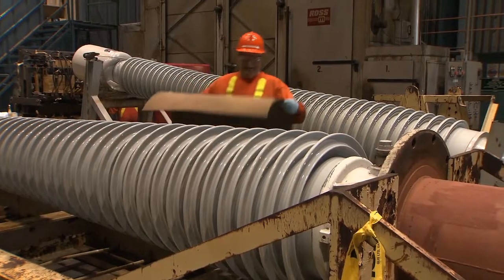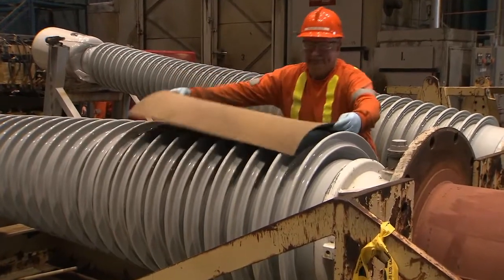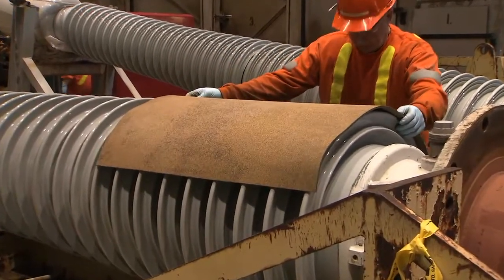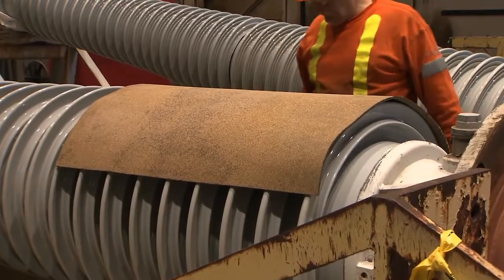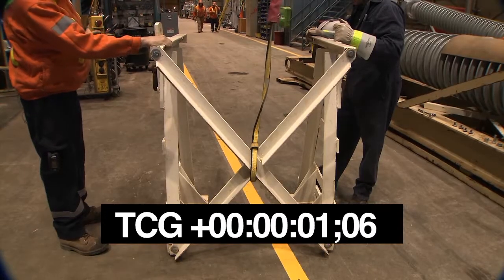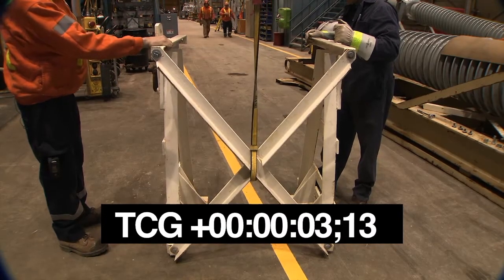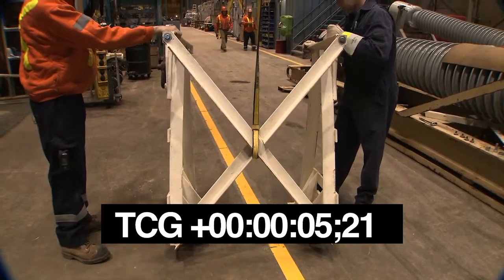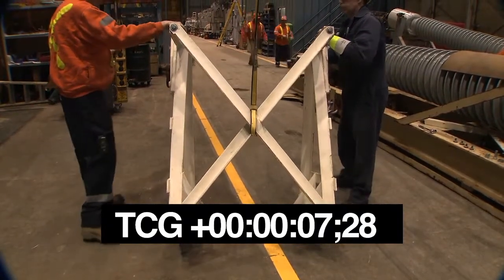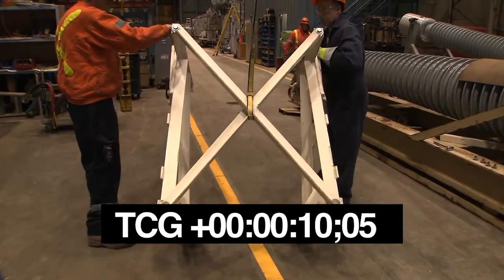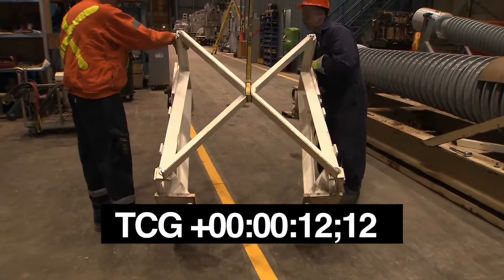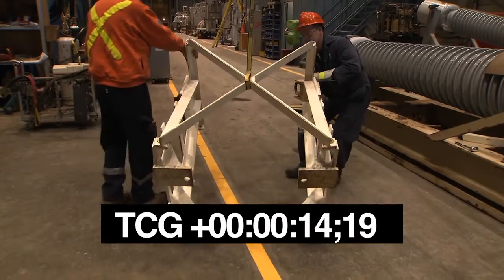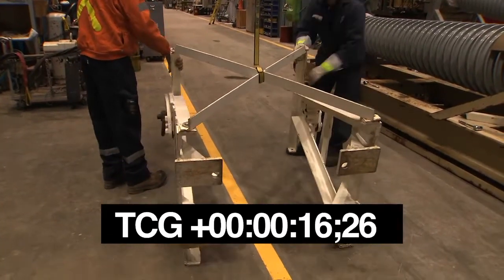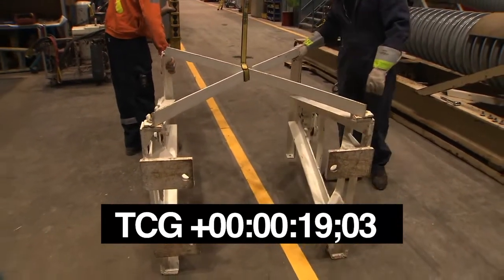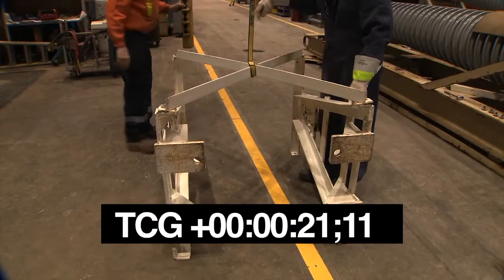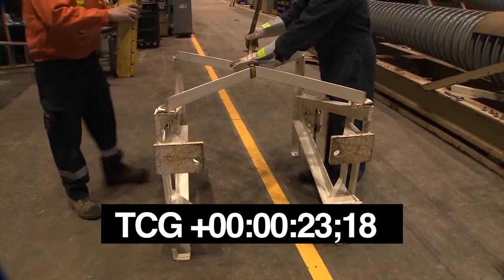Place a sheet of cork padding over the porcelain just above the mounting flange to protect the porcelain from directly contacting the lifting jig when it is attached. Loop one end of a lifting sling, having the appropriate weight rating capacity, around the junction of the remaining crossmember on the lifting jig. Attach the other end to the hoist hook, and then turn the jig so that the remaining crossmember is on top, and the 4 rectangular plates, each having a hole near the inner edge, are facing north, and the jig rests on the floor.